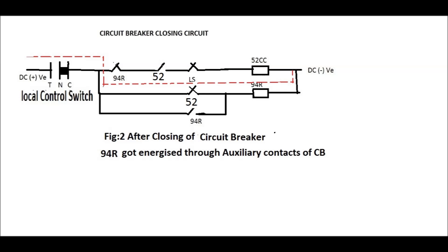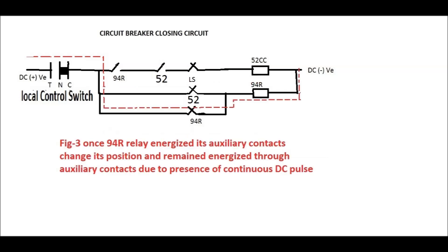As soon as the 94R relay operates, it will operate its auxiliary contacts and change their positions. It will then remain in the energized condition through its own 94R contact, as shown by the red dotted line. Therefore, no further DC pulse will go to the closing coil whether the circuit breaker is in the closed or tripped condition.